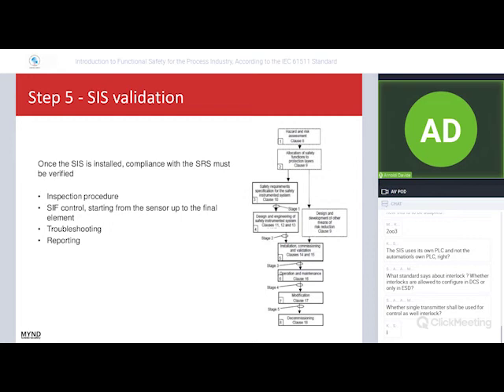Validation is the test on site of the performance of the safety instrument function. You need some expertise to realize the safety instrument system validation, because it's the last point. After that, you put the safety instrument system in operation, but you have to be sure to respect the SIL level by SIL allocation, the safety requirement specification, and also the SIL verification.